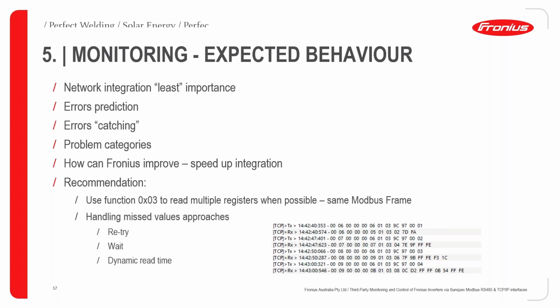I'm sharing here, as we've shared previously, a response from a client-master server communication over TCP. You can send a request and see how quickly it responds. A lot of information can be gathered from this log file. I'll show you how to do that, but timing, addresses, registers, data values, and exceptions can all be troubleshot through a simple log file.